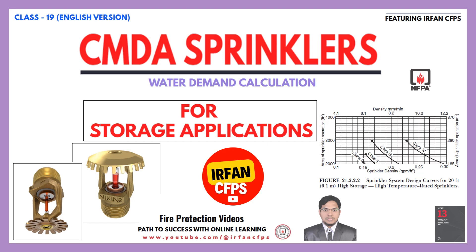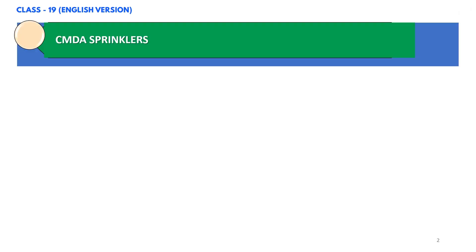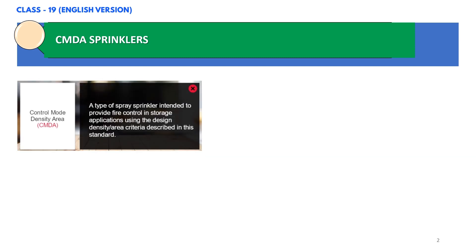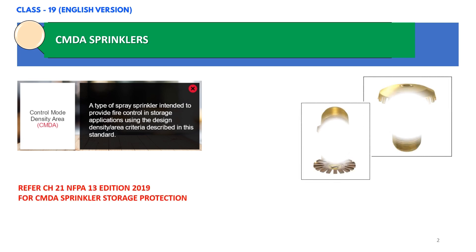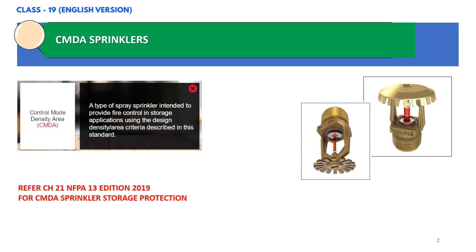Let us try to understand what exactly is a CMDA sprinkler. CMDA stands for Control Mode Density Area, and these sprinklers refer to a specific type of sprinkler listed for control of fires in storage applications. In other words, as you can see on your screen, it is a type of spray sprinkler intended to provide fire control in storage applications using the design density area criteria described in NFPA 13 standard.